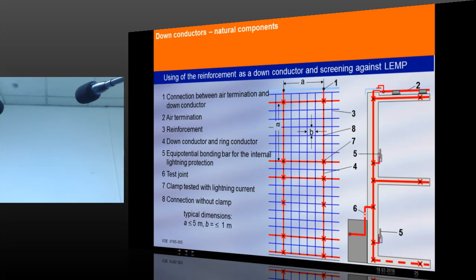Now, you see here, for a modern building, this is supposed to be the down conductor, and what is recommended in this standard is a strong connection at every 5 meters. This distance A is 5 meters, and the small distance is B. So every 5 meters, you need to have a strong connection with a clamp or with a weld tested to withstand that particular lightning current.